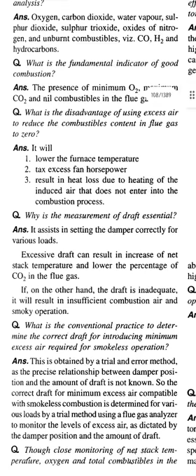Question. Why is the measurement of draft essential? Answer. It assists in setting the damper correctly for various loads. Excessive draft can result in increasing of net stack temperature and lower the percentage of CO2 in the flue gas. If on the other hand the draft is inadequate, it will result in insufficient combustion air and smoky operation.